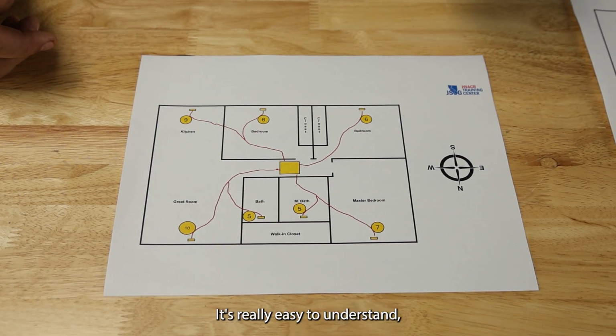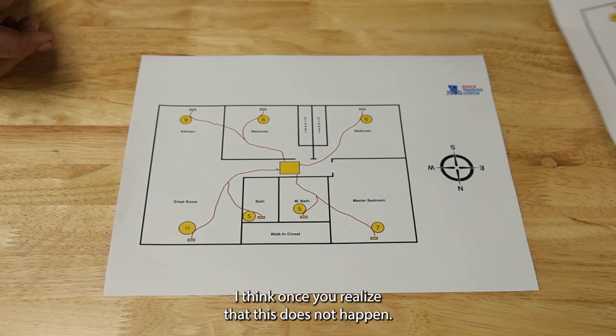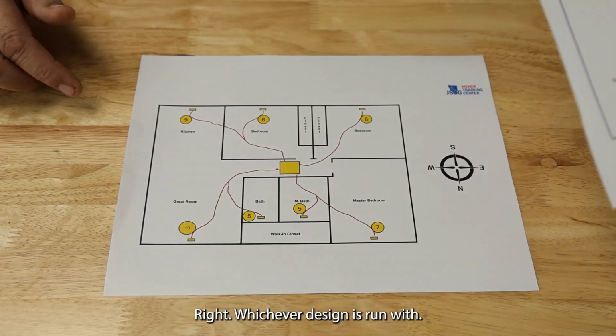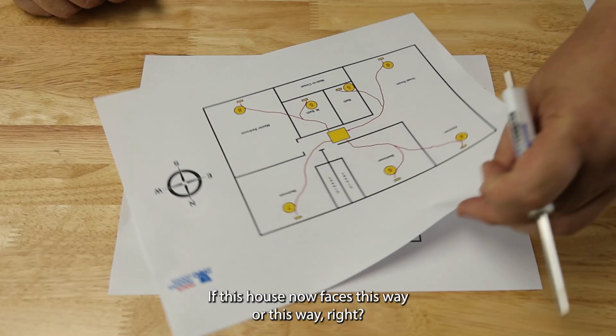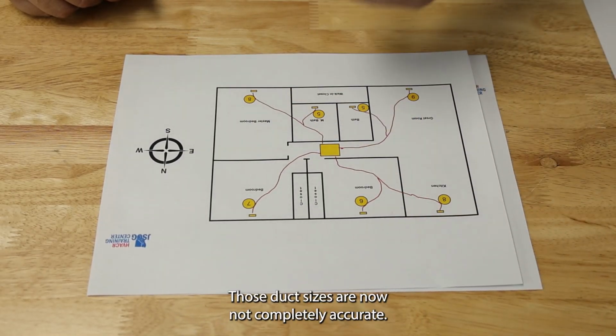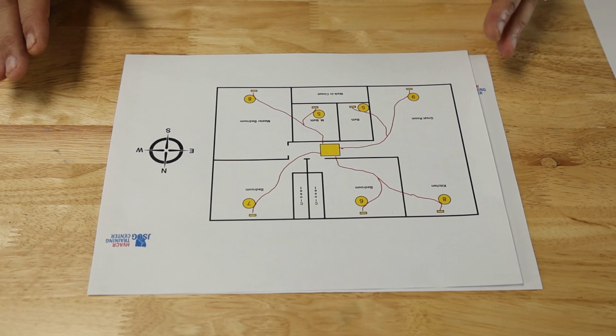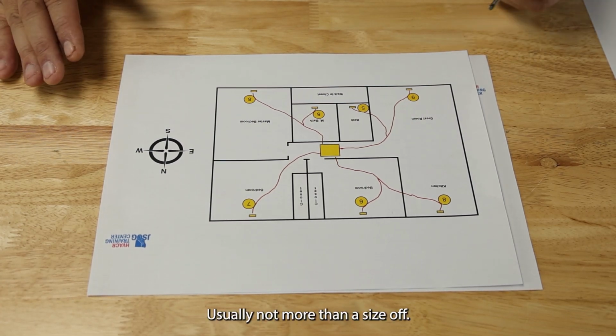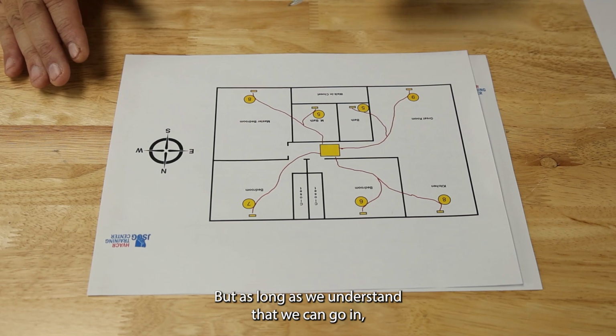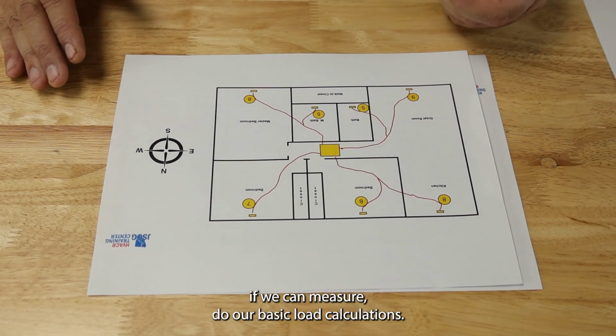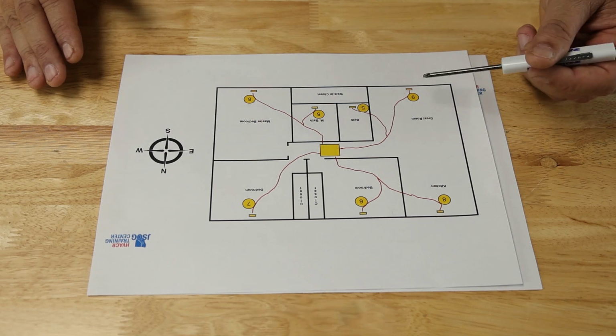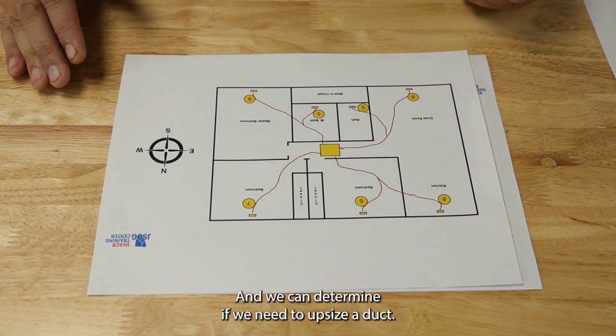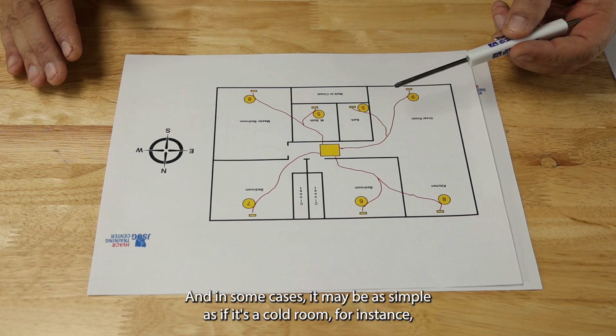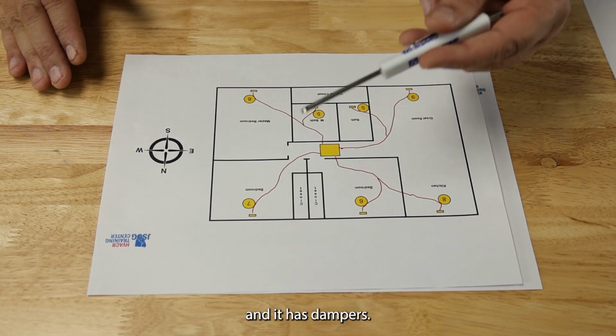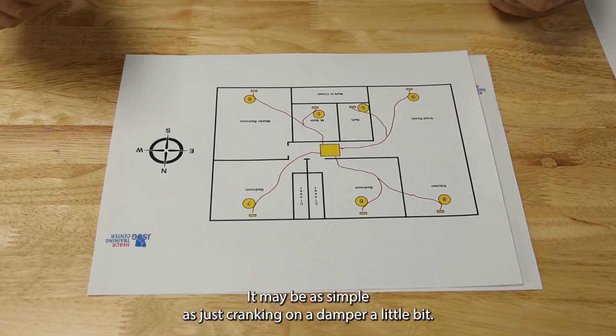It's really easy to understand, I think, once you realize that this does not happen, right? Whichever design is run with, if this house now faces this way or this way, right, those duct sizes are now not completely accurate. Usually not more than a size off, but as long as we understand that, we can go in and if we can measure, do our basic load calculations, and we can determine if we need to upsize a duct. And in some cases, if it's a cold room, for instance, and it has dampers, it may be as simple as just cranking on a damper a little bit.